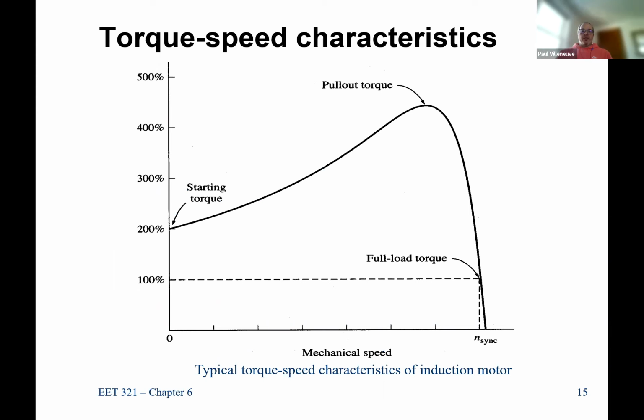let's look at what are called our torque versus speed characteristics. So this is, again, the beauty or the advantage of how we can operate or work with an induction machine. So any mechanical load has what's called a torque versus speed characteristic. It may not necessarily be developed in curves, but you can actually get data based on the size of the pump that you're doing, how much water it's pushing, and it's going to demand a certain amount of torque. Well, you want to be able to start that pump. So one of the things you have to do is you've got a motor that has water sitting on it, and it's got to be able to spin the impeller, or whatever the pumping system is. It's got to be able to spin that up.